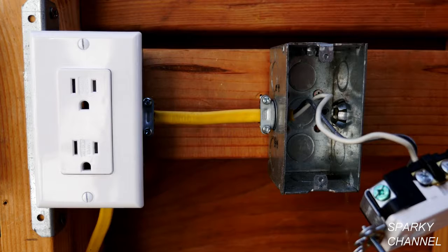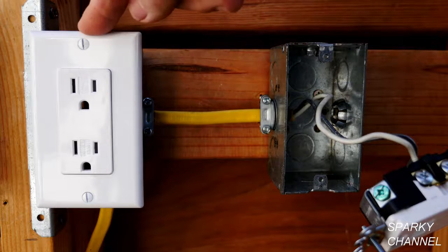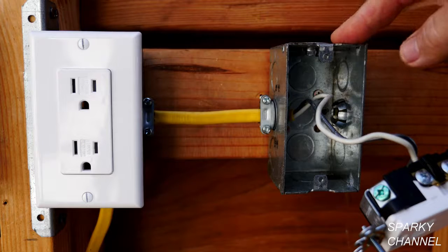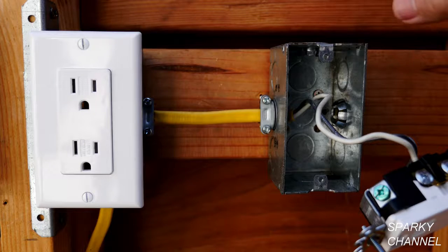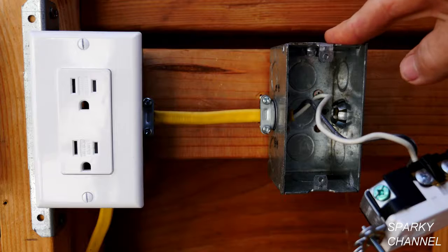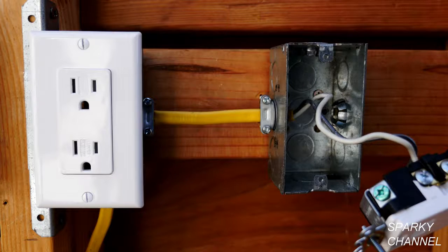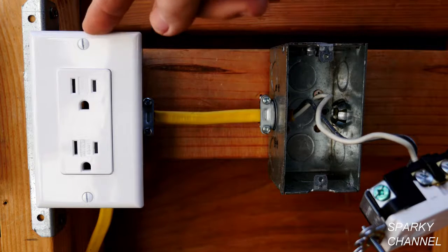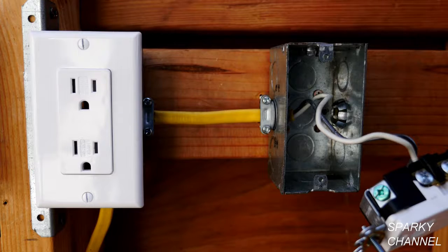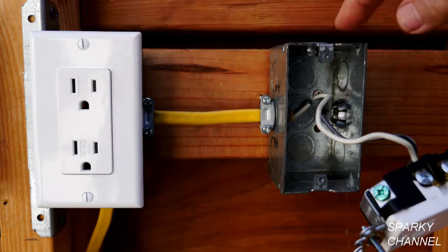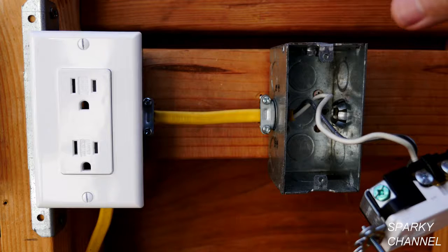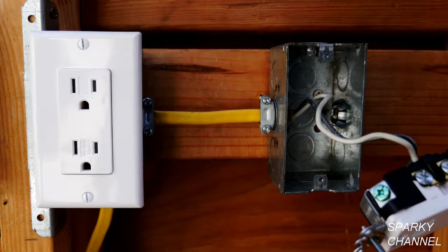So it may be possible to remove the cable going from this receptacle to this receptacle and bring a ground wire to this one. But to do that, we're going to have to check for continuity. That will tell us if this receptacle is the next upstream receptacle from this one, that is, one receptacle closer to the main panel. If so, we can change out the cable going from this box to this box and bring a ground to this box.